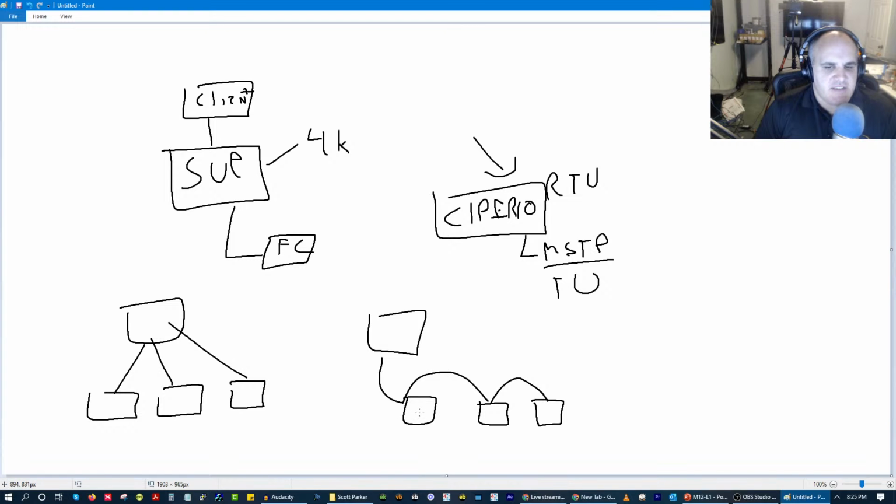So that means if I lose power to this IP controller right here, then I am going to lose the ability to connect to this controller as well, because electrically the signal will not continue. It's not like RS-485 where you can lose power to a controller and the signal is just going to continue on. Now, a lot of manufacturers are starting to recognize and address this, but it's still something to be cognizant of.